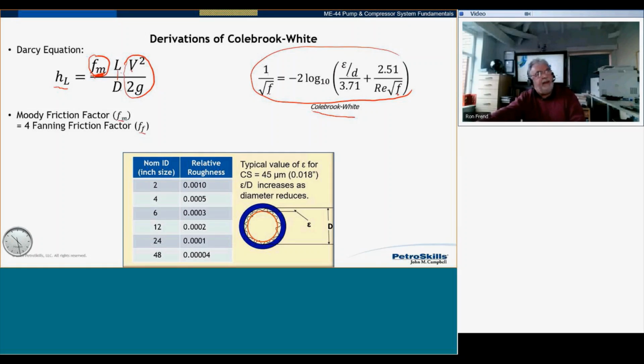But a couple of things I want to show you now. Look what's in here. Right here is the Reynolds number. I need the Reynolds number. And what I've also got is something else here not everyone's familiar with. This is the relative roughness on the inside of the pipe. And relative roughness is that epsilon, that is the absolute roughness. Now for carbon steel, that's going to be around about 45 microns or 0.018 inches, approximately. We divide that by the inside diameter of the pipe, and what we get is something called the relative roughness. If you look at the different sizes of pipes here, you'll see that the relative roughness decreases as the pipe size increases. And of course that makes sense, because the absolute roughness stays the same because it's carbon steel, but you divide it by a diameter, so bigger diameters have less relative roughness. It all makes sense.